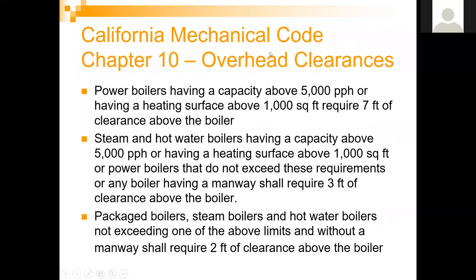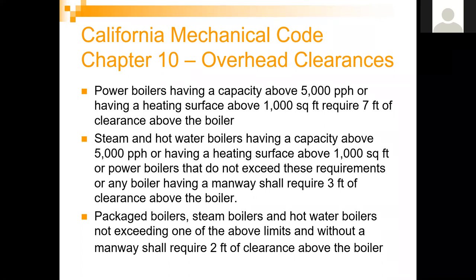California Mechanical Code Chapter 10 covers overhead clearances. Power boilers having capacity above 5,000 pounds per hour or heating surface above 1,000 square feet require seven feet of clearance above the boiler. Steam and hot water boilers with capacity above 5,000 or heating surface above 1,000 square feet, or powered boilers not exceeding those limits, require three feet clear above the boiler. Packaged steam boilers and hot water boilers not exceeding the above limits and without a manway only require two feet clearance above.